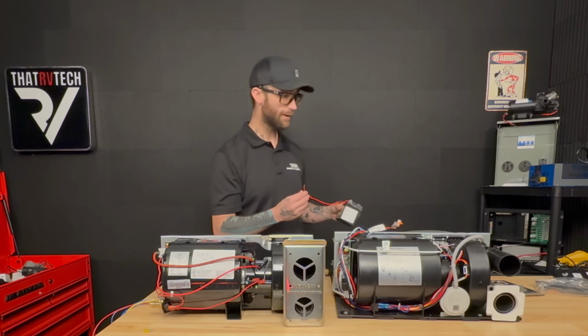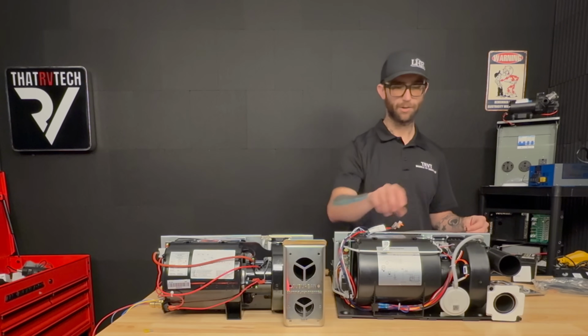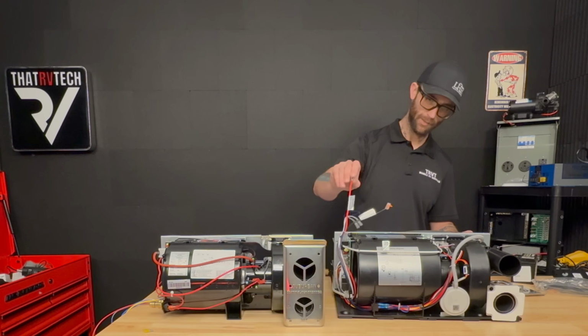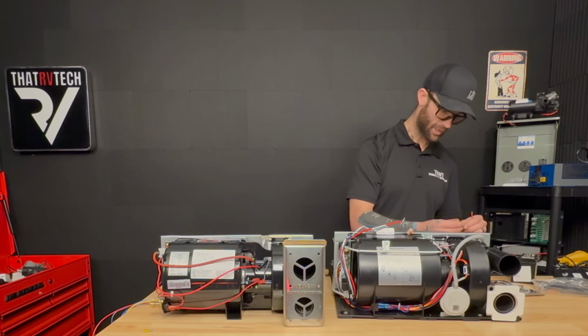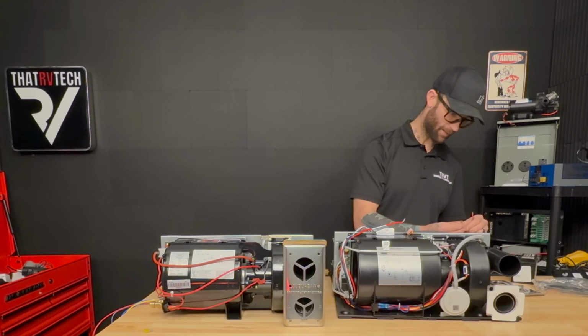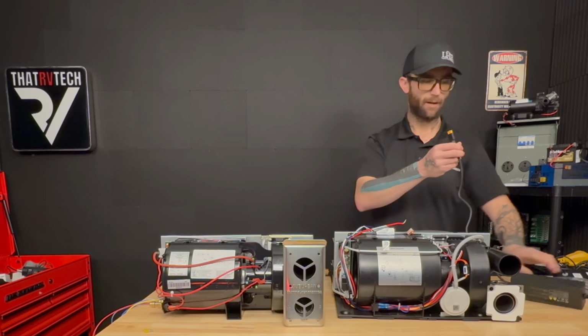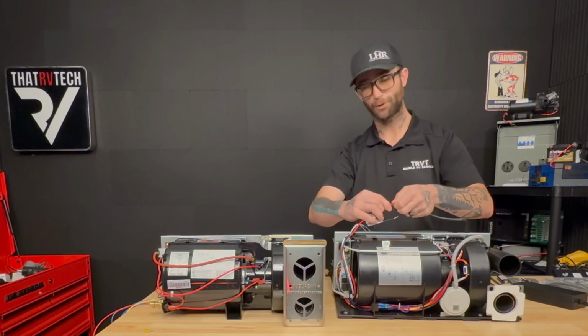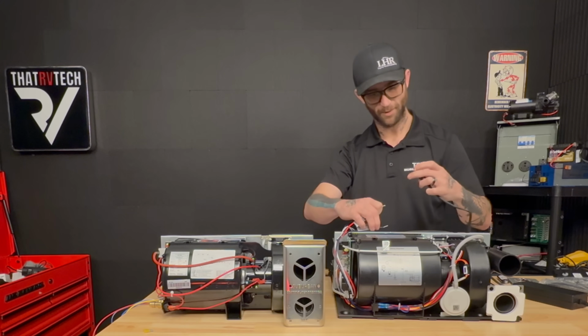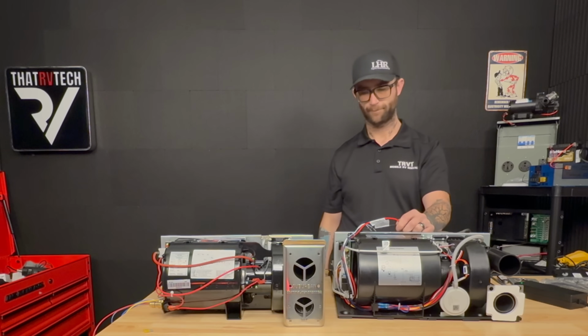That battery is way too dead. As soon as that igniter came on, it just killed the fan motor. So I guess it's time to change my little bench test battery, if you will. Don't you worry, I've got all kinds of stuff around here. So we'll try this again with a known good power source.